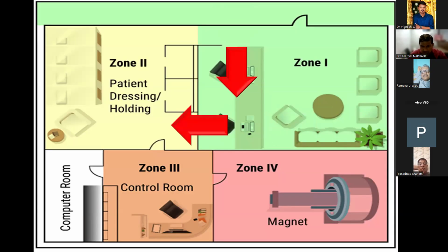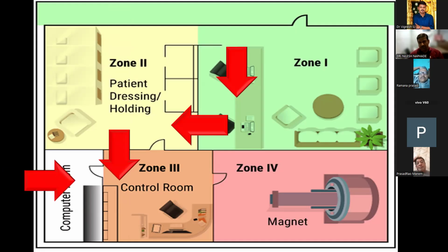Zone 2 is from where the dangerous area begins. The magnetic effect starts taking charge. Zone 2 is where the patients are held. The next patient is waiting. The patient is given a change of clothes. The relatives are told about removing all metallic objects, metallic belongings. This is zone 2. Zone 3 is the console room or the control room from where the radiologists or the technicians control the machine. So through a glass, they are seeing the machine and they are seeing the patient. And this is zone 4, where the actual MRI machine, or the magnet within the machine, is located.